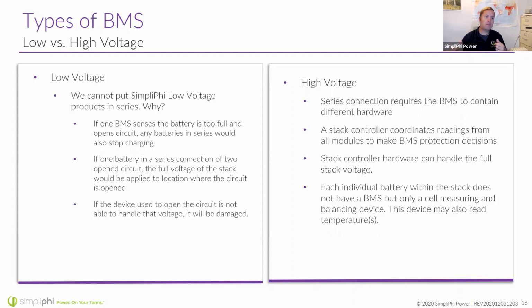So if you have a bunch of 48-volt batteries in series, stacking that voltage up, and one of those batteries is full and decides to open circuit, now that battery is seeing the full stack voltage. If that battery management system isn't rated for that higher voltage, it can fry that battery management system.